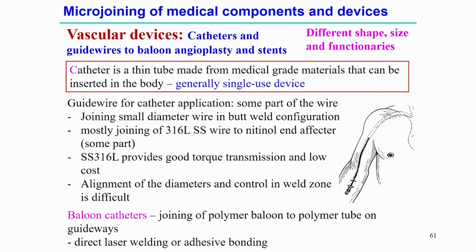So, in this case, sometimes with single use devices, the high cost nickel titanium alloy can be used in these medical devices. Sometimes it is necessary to replace some part of the nickel titanium wire or tube with a stainless steel tube. That can be the cost effective methodology.